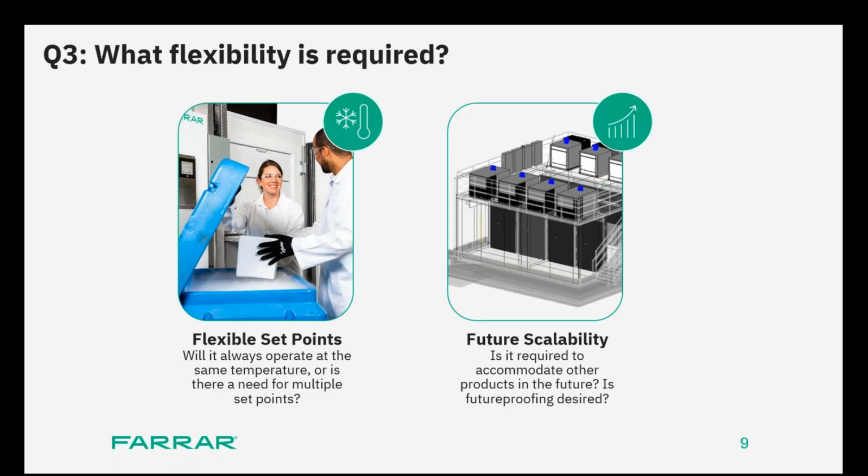And finally, when the finished products are done, I can just reset the set point temperature, bring it up to +5, and we're all done. I was like, yeah, that would be a great accommodation for a given specific solution with a cold storage system.